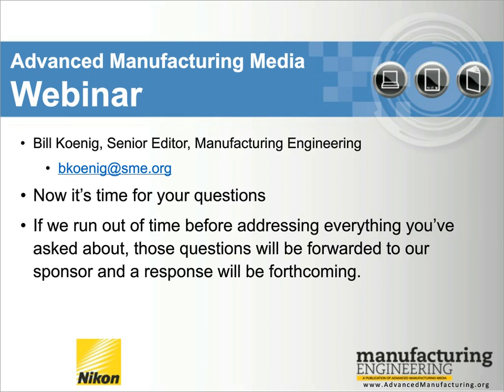Okay. Another question just came in. What is the precision with tactile, laser, and vision inspections? Yep. So the overall accuracy of these machines is given as an MPE, so maximum permissible error.